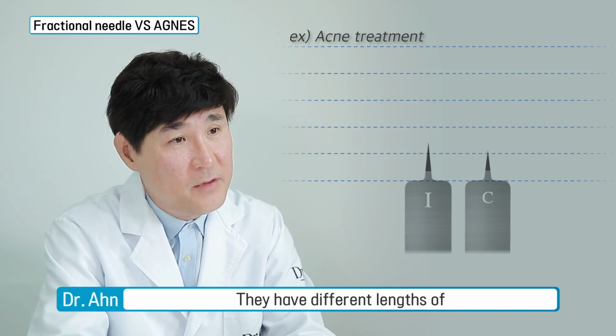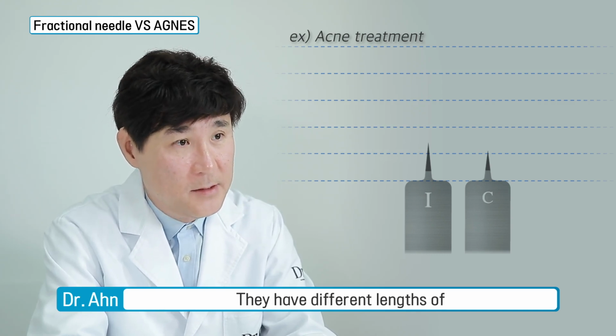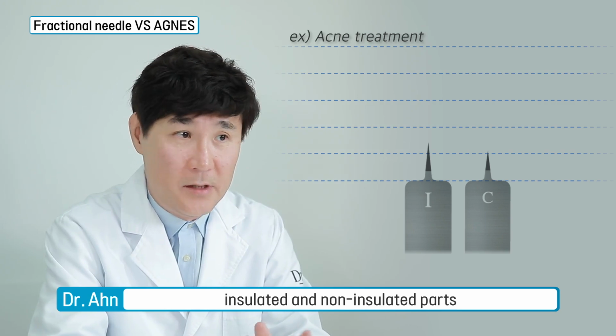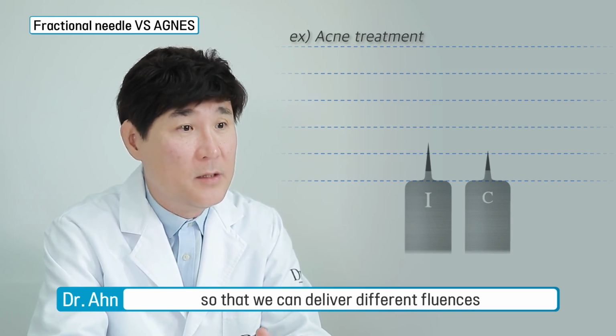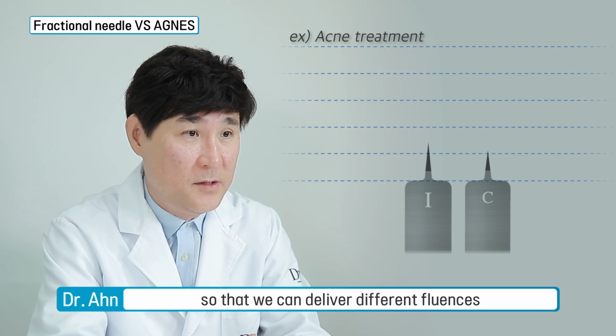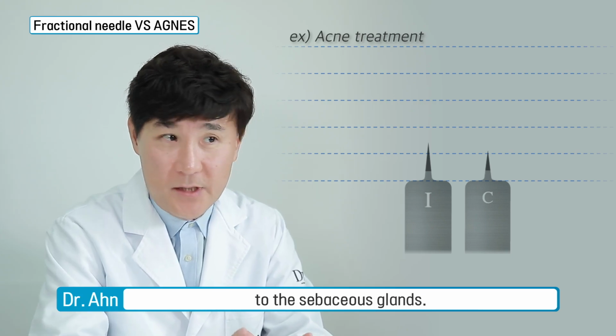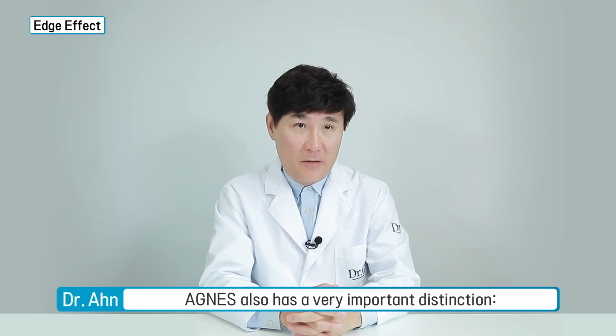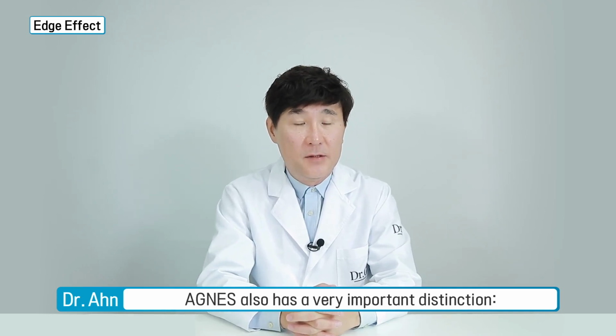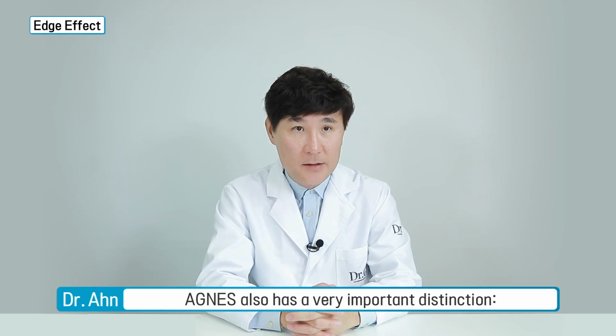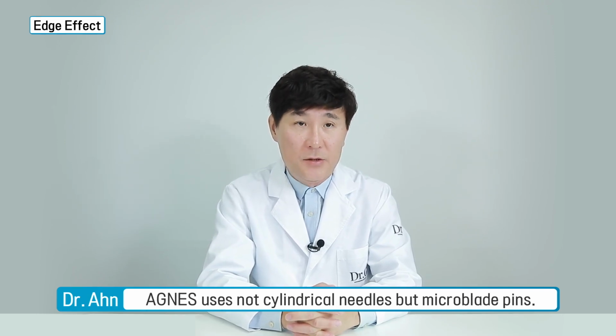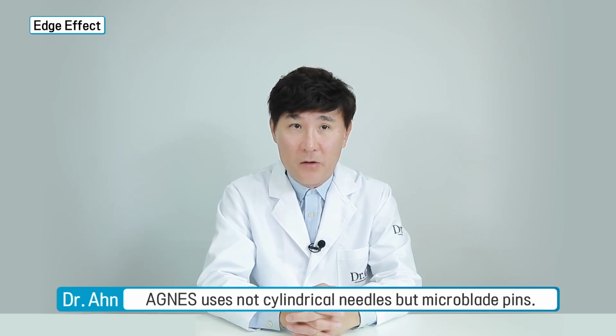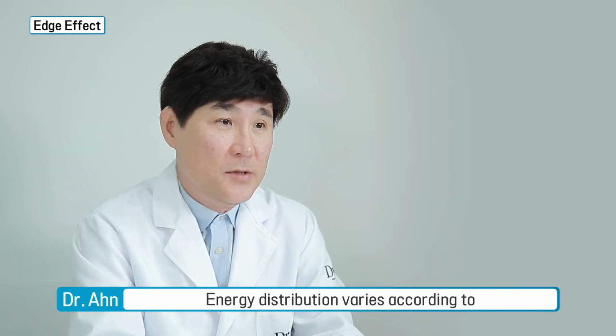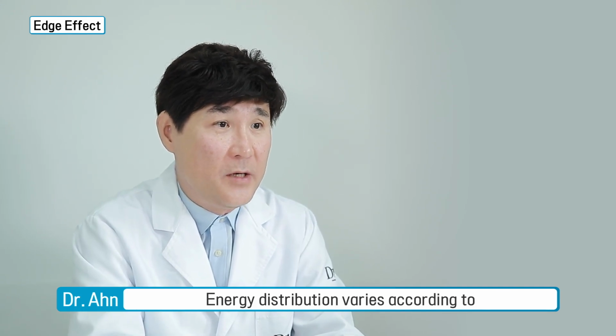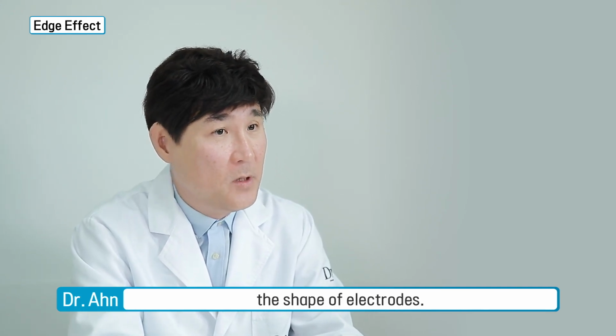They differ in length and in the non-insulated part, so that we can deliver different fluences to the sebaceous gland. There is one very important difference of Agnes: it uses not a cylindrical needle but a microblade pin, because energy distribution varies according to the shape of the electrode.